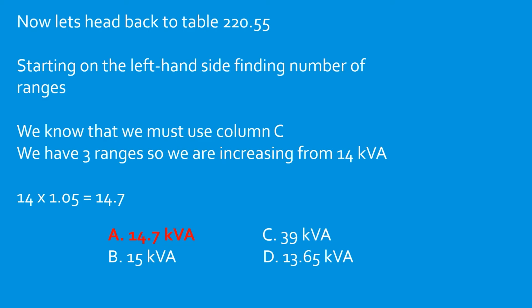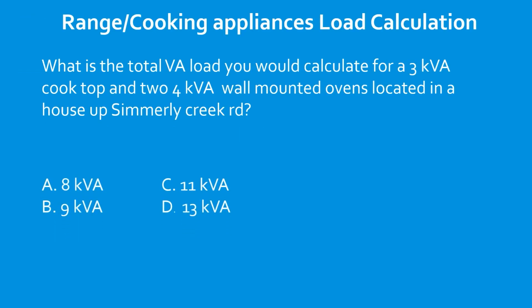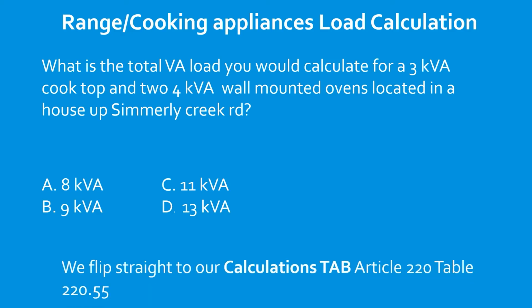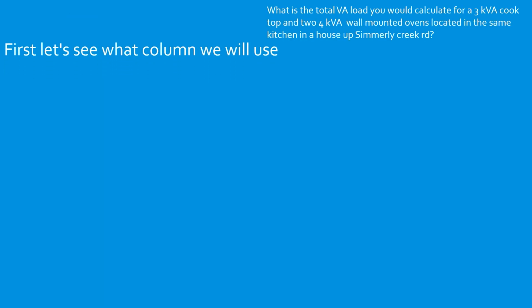Let's get to it. What is the total VA load you would calculate for a 3 kVA cooktop and 2 4 kVA wall-mounted ovens located in a house up Simmerly Creek Road? Well, the first thing that we're going to do is use our calculations tab to head to Article 220, Table 220.55. All right, so the first thing we're going to do is figure out what column we're using. So we reread our question. We have a 3 kVA cooktop and 2 4 kVAs. So it looks like we're going to be using columns A and B.